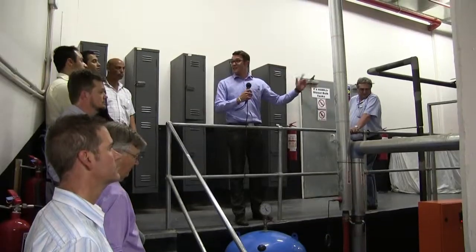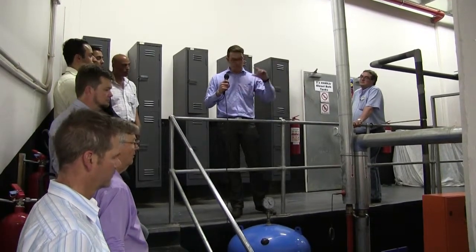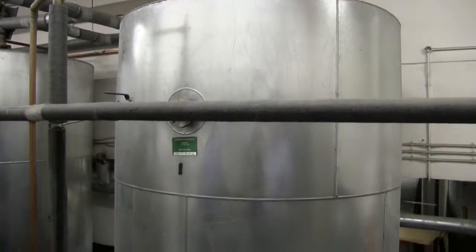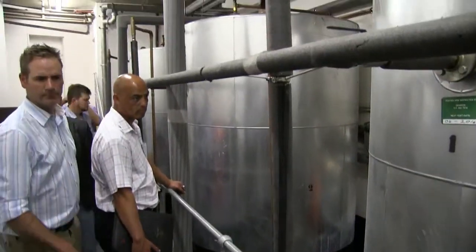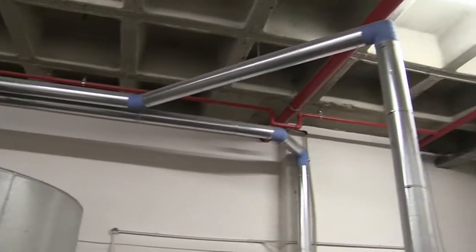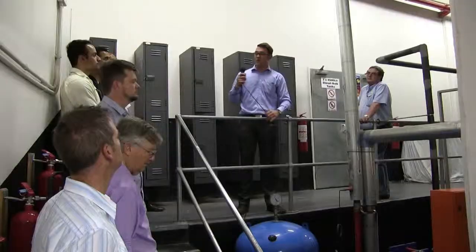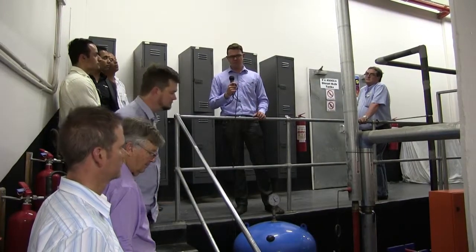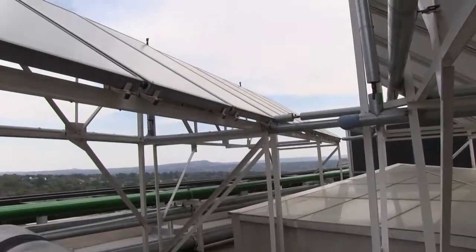liters each. The first tank doesn't have an element that switches on with temperature. It just stays the same temperature as what the solar provides. The second tank has an element which is set to switch on if the temperature reaches 40 degrees Celsius. And then the final tank that feeds into the hotel's whole reticulation system, that element switches on when the temperature goes below 60 degrees Celsius.